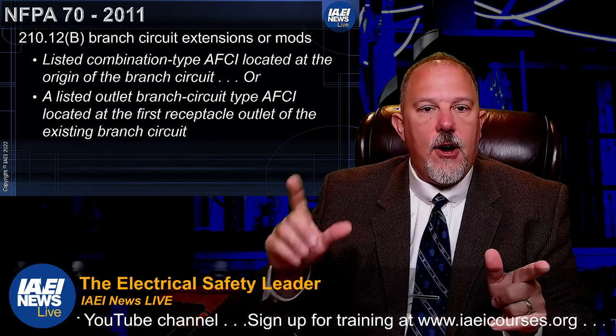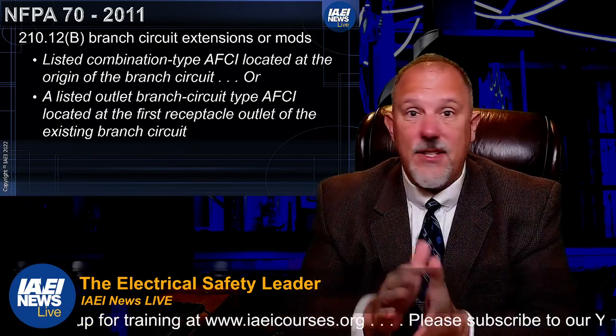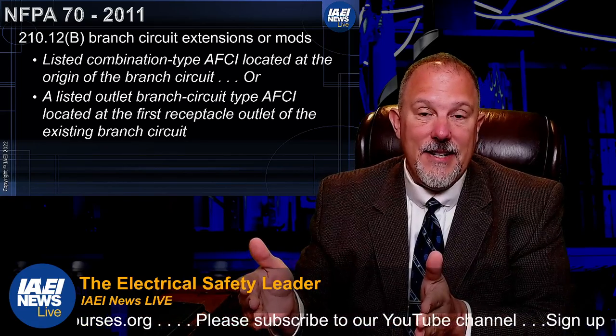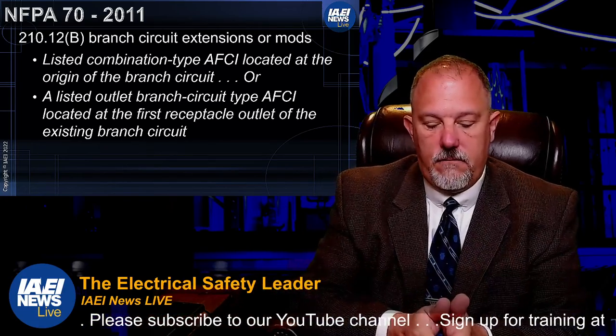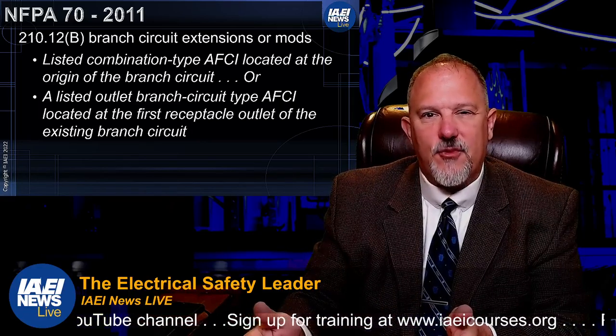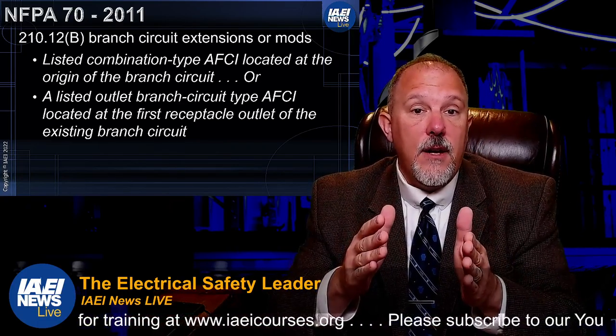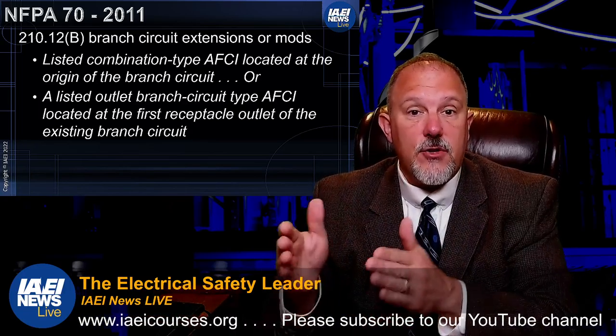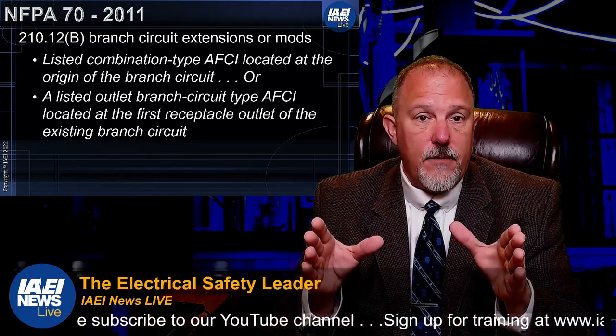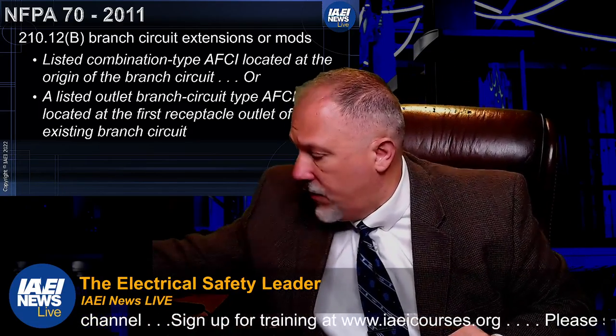By using outlet branch circuit type AFCIs at the first outlet in existing homes, you move the protection point further downstream rather than fully addressing old wiring, but you still get detection of problems downstream. This was the first time a requirement appeared in the code for branch circuit extensions or modifications — any such work in the listed rooms would now mandate AFCI protection.